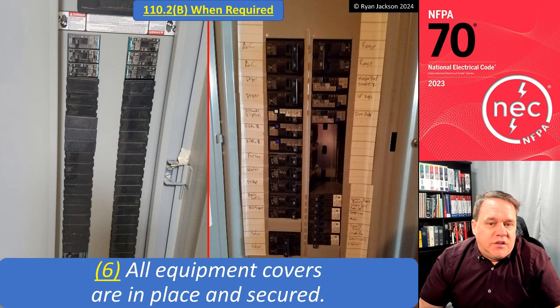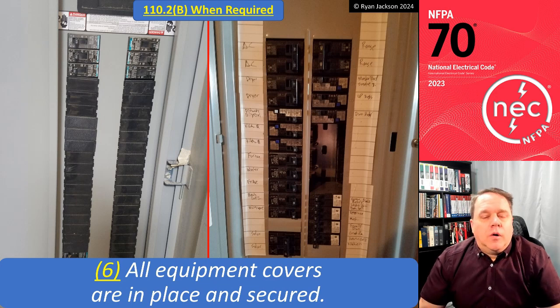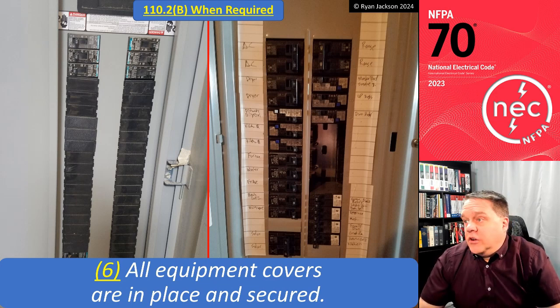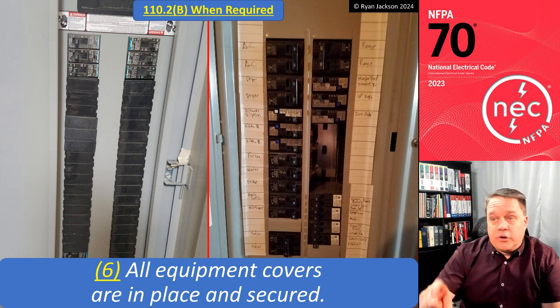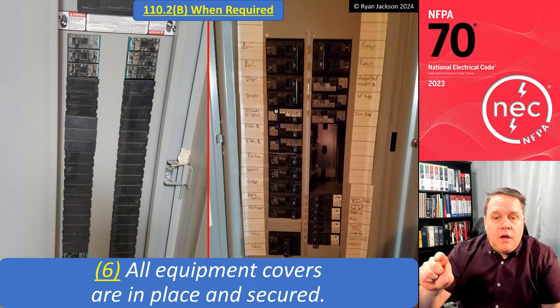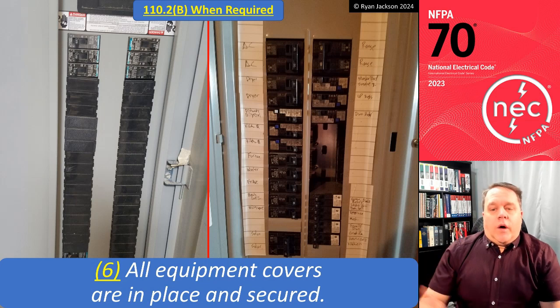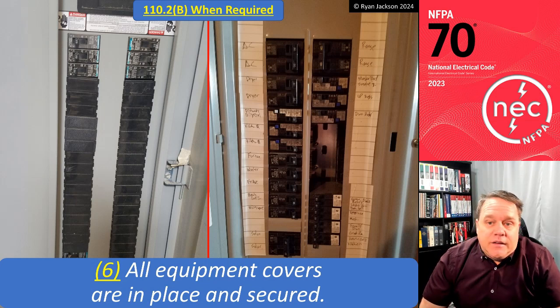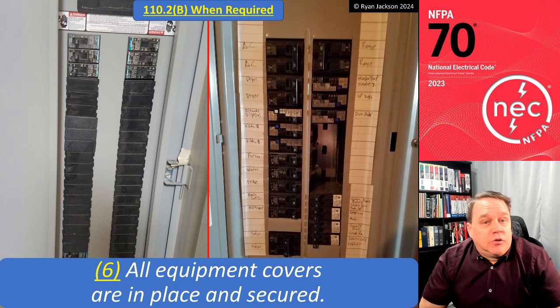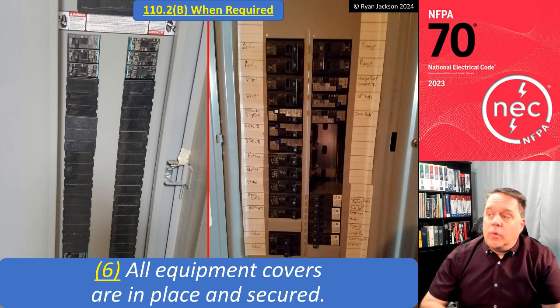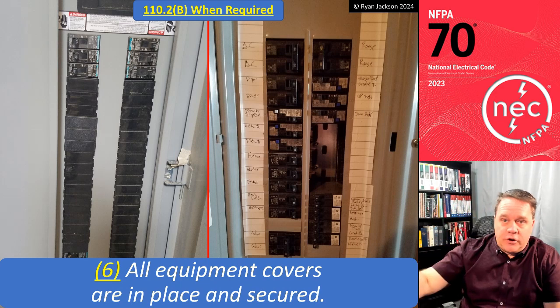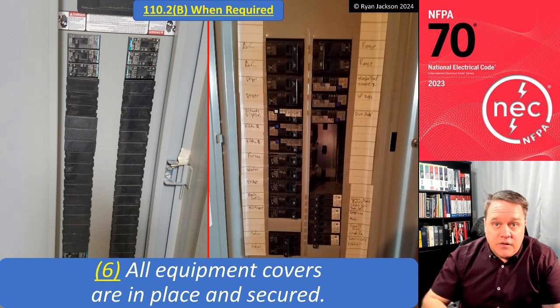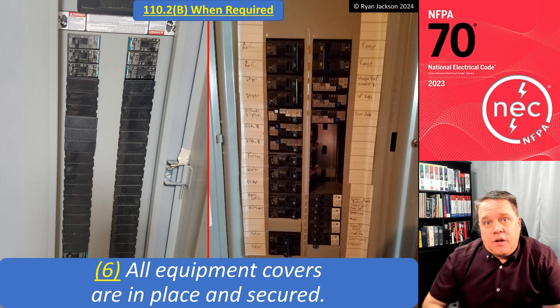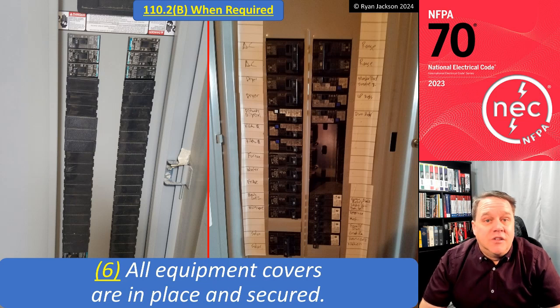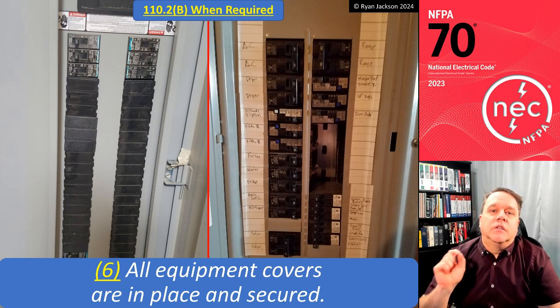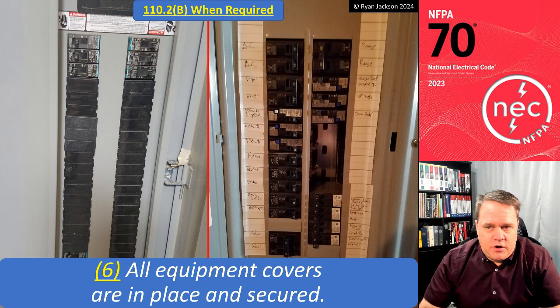Covers are in place and secured. All right, so over here on the left, that panel board has a lot of circuit breaker fillers, right, blanks, but at least they're there. The one on the right, is there normal operation of that equipment? Absolutely not, right? We don't know what kind of critters and objects and things have gotten inside of that panel. So I can't just walk up to it and turn on and off the breaker because that is not a normal operating condition because the covers are not in place and secured.